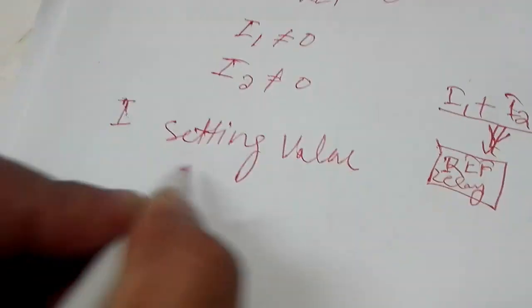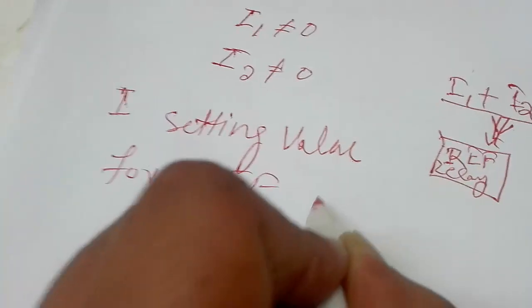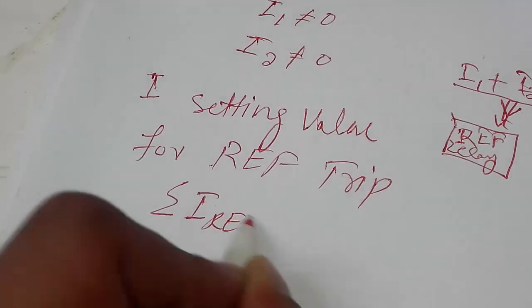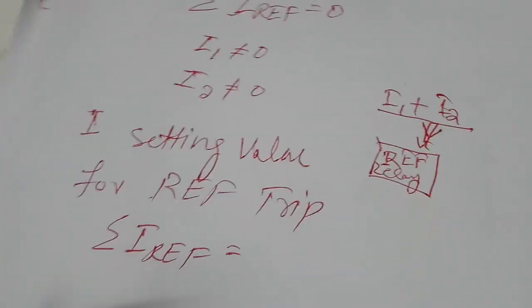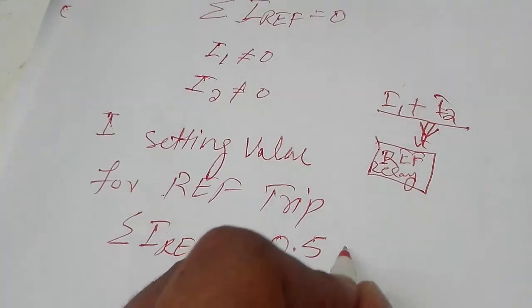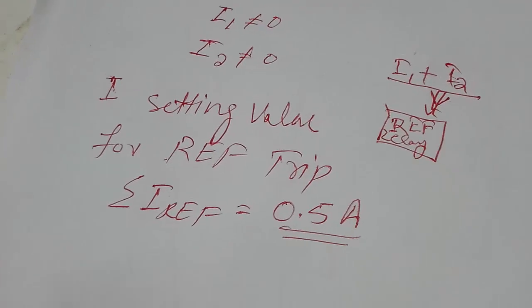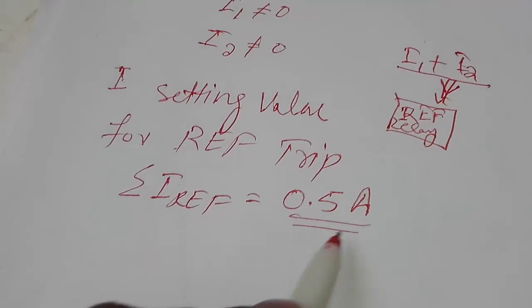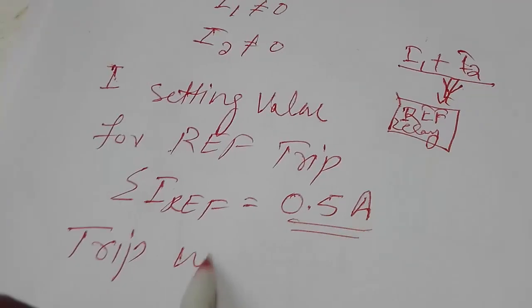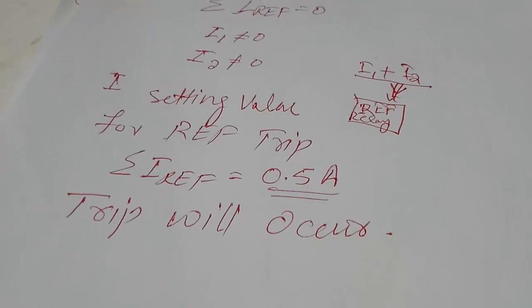The setting value for the REF trip: the summation of IREF is set to 0.5 ampere. So when we inject current and this summation reaches 0.5 ampere, the relay will pick up and the trip will occur. Now we will show this condition practically from the relay.